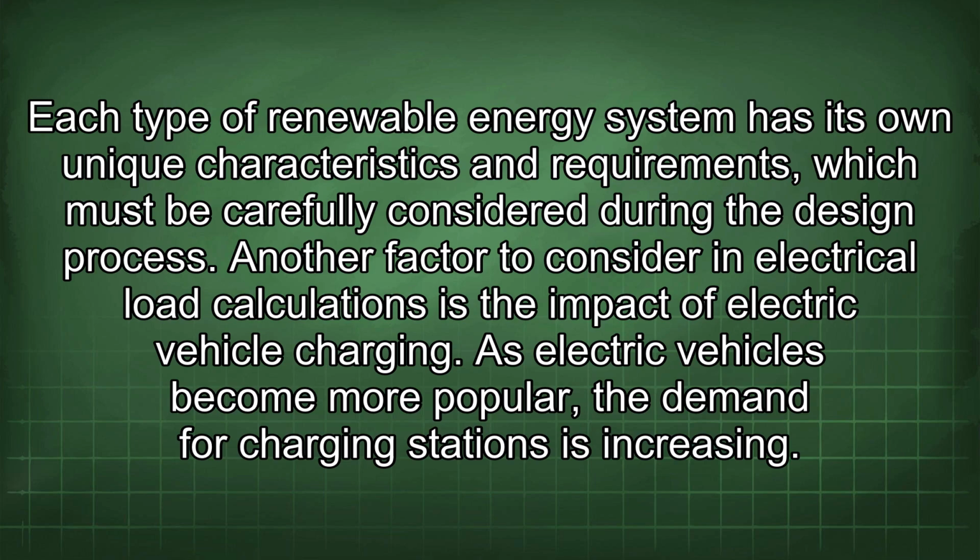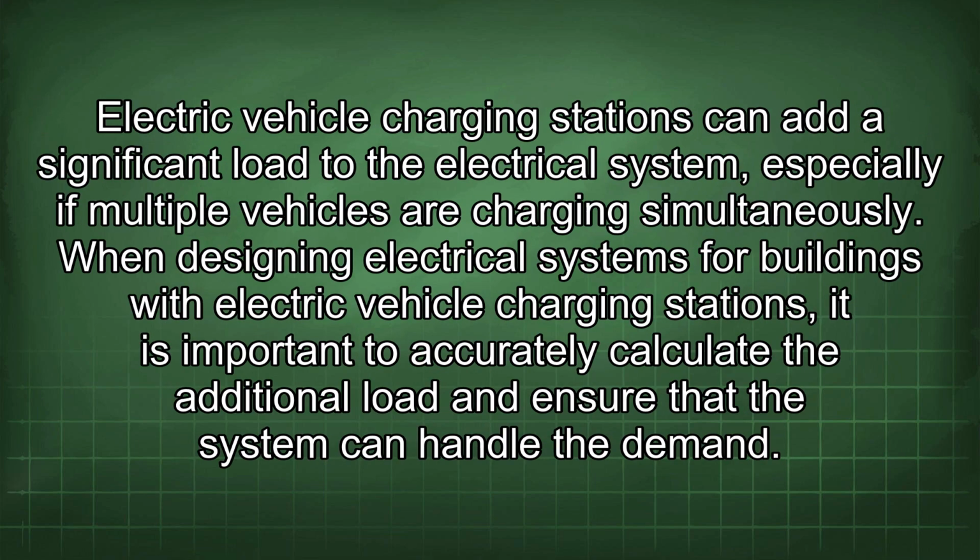Another factor to consider in electrical load calculations is the impact of electric vehicle charging. As electric vehicles become more popular, the demand for charging stations is increasing. Electric vehicle charging stations can add a significant load to the electrical system, especially if multiple vehicles are charging simultaneously. When designing electrical systems for buildings with electric vehicle charging stations, it is important to accurately calculate the additional load and ensure that the system can handle the demand.